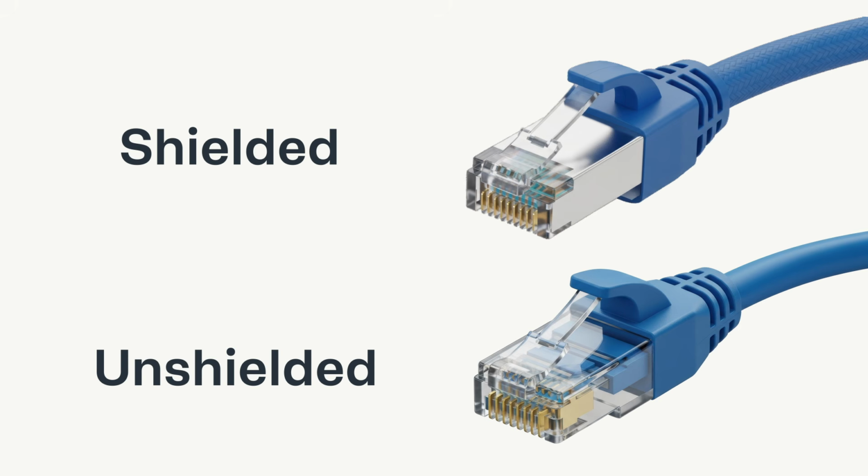Furthermore, and this is a very big difference, for the RJ45 plugs, so for the standard communication plugs, there are shielded versions and non-shielded versions. Please always make sure, and this is also our recommendation, to use shielded RJ45 plugs. You can see that very easily on the plug itself. There is either a metal cover, a metal shield around the connector, or it is just a standard plastic shell, so that means that the RJ45 plug is not shielded. And we recommend you to always use the RJ45 plug with the metal shield.